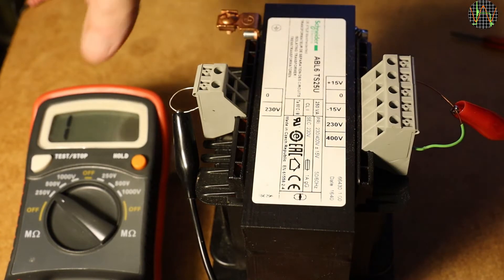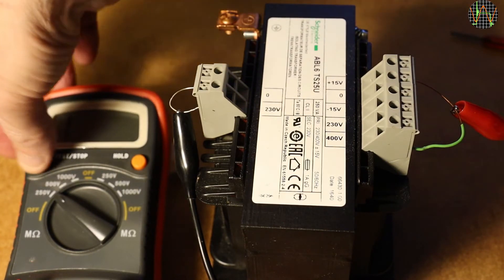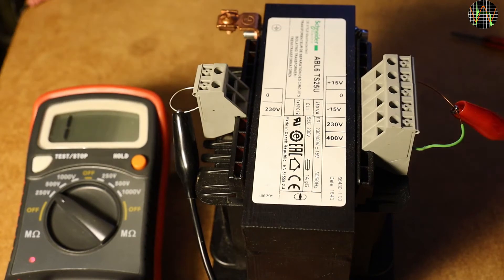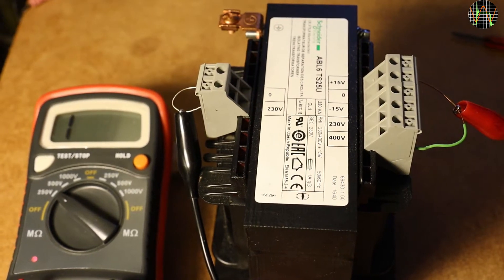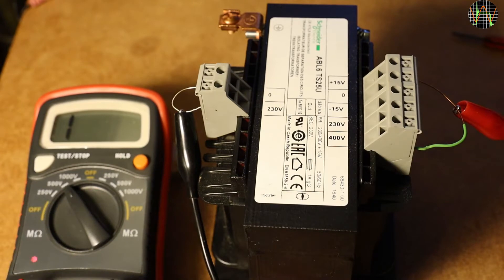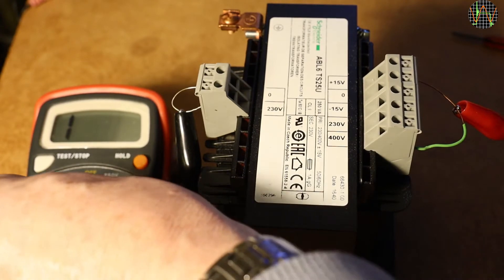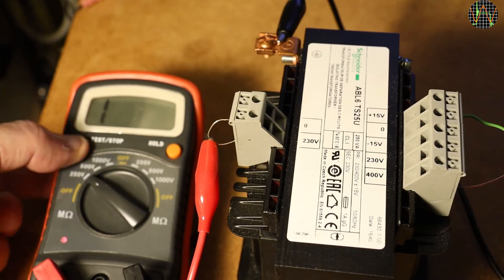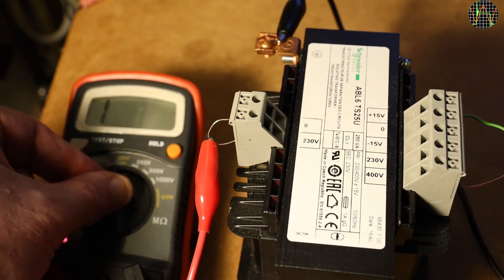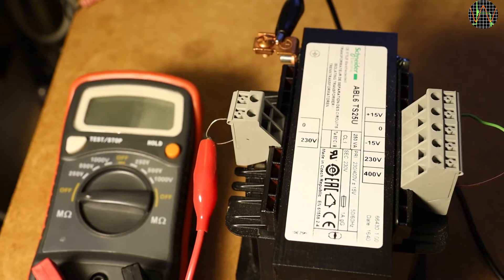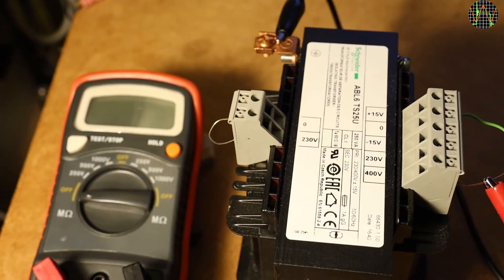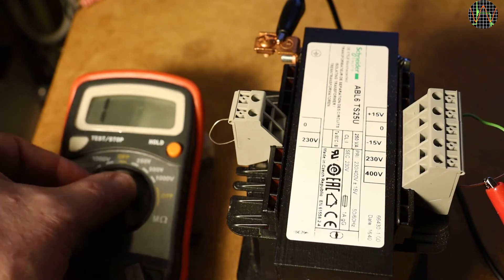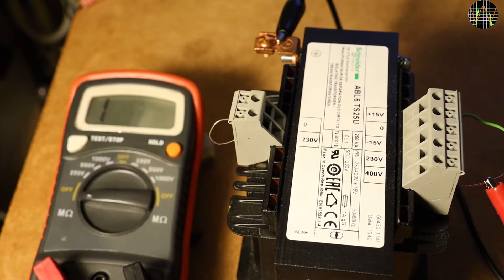Let me know if you would be interested in a review of that instrument. I tested the isolation between primary and secondary with 250V, 500V and 1000V DC and found no problem. I then tested the isolation of the secondary winding against the transformer's earth terminal using all three voltages and then repeated the test with the primary winding, again finding no issues which means the transformer is good to go.